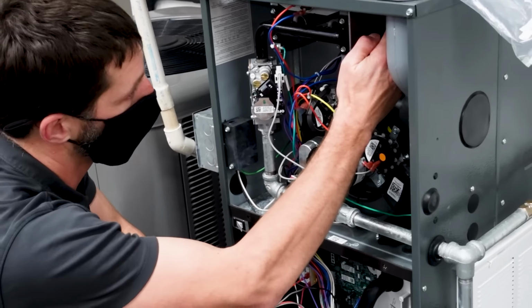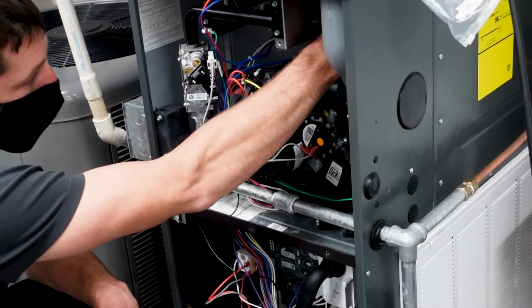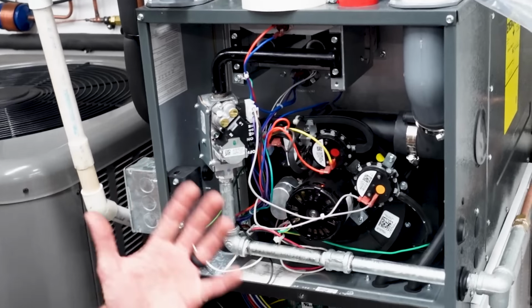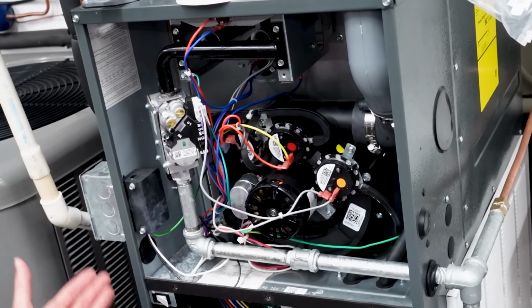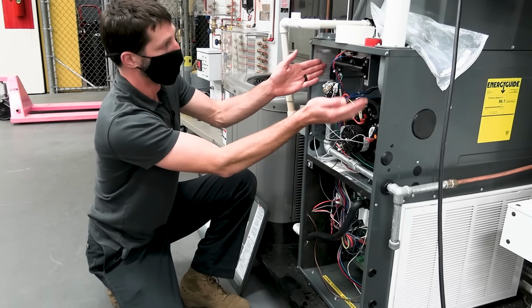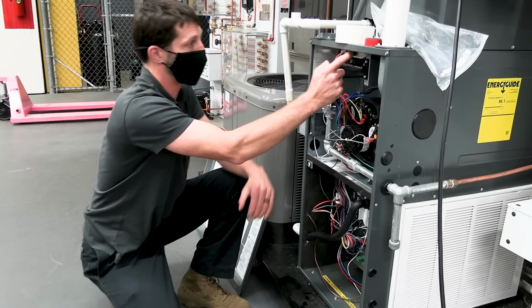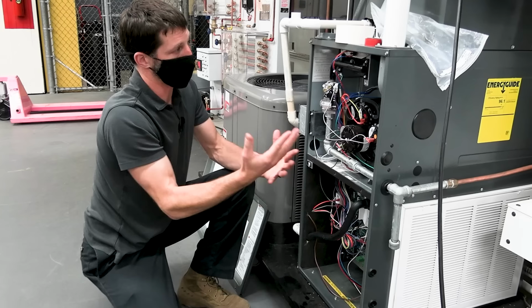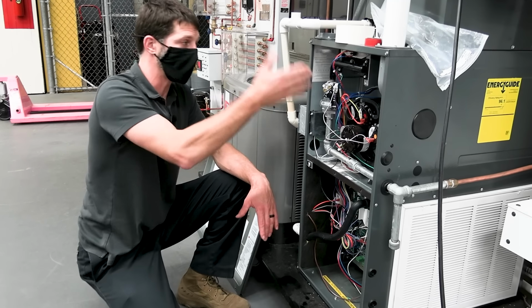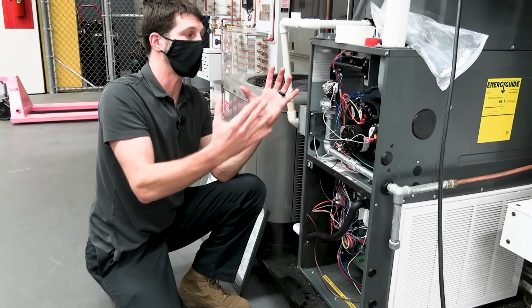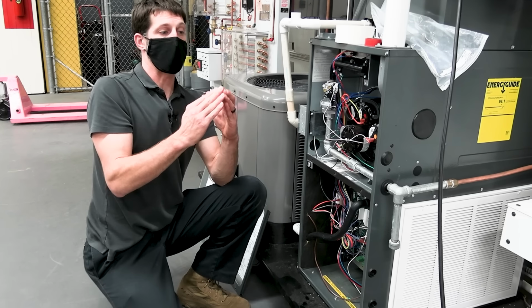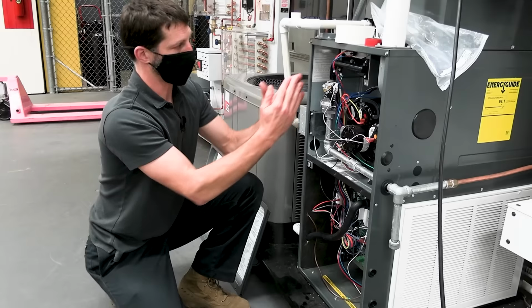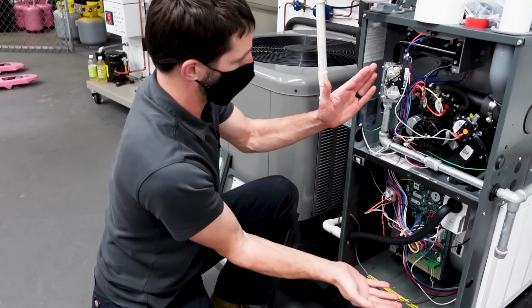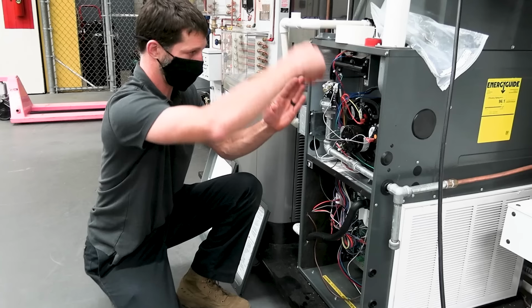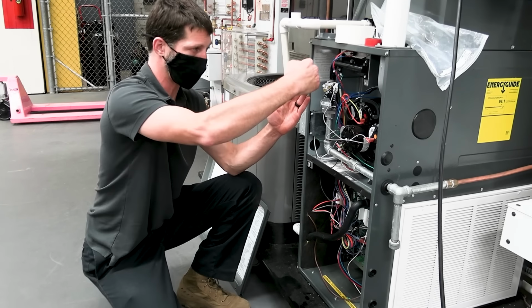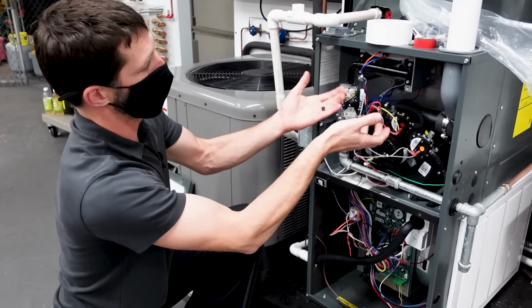It could be that the heat exchanger or this plate right here is pulled away from the heat exchanger. There's a multitude of things, but basically the air from the blower motor is somehow pushing the flame back to the flame rollout switch. That's really what the problem is. A lot of times it is a crack in the heat exchanger. It may not show up until the heat exchanger is hot and the crack opens up. Then the blower air enters in because it's entering into the lower pressure area and then pushing the flames back out.